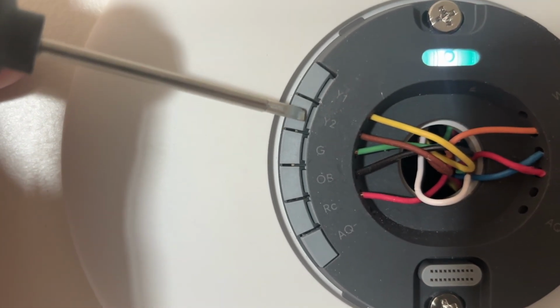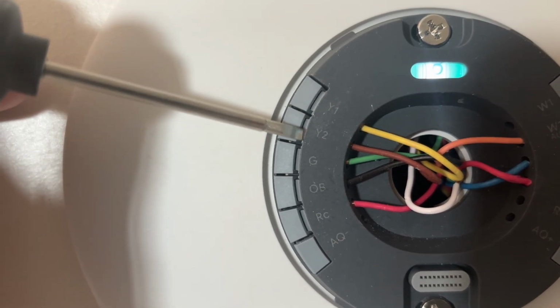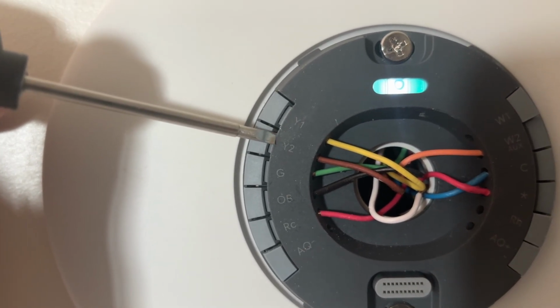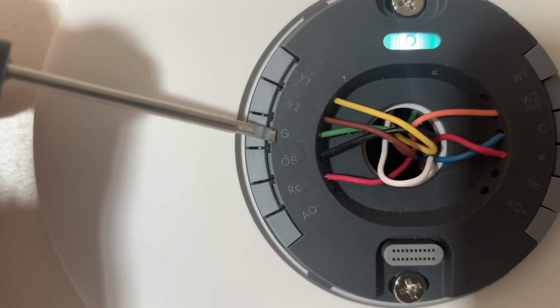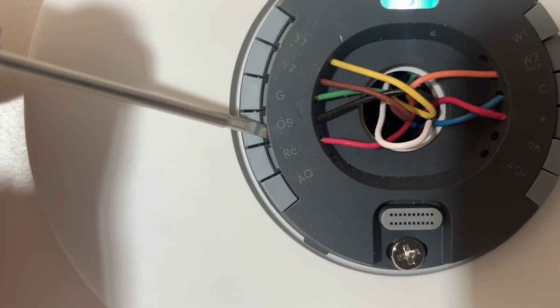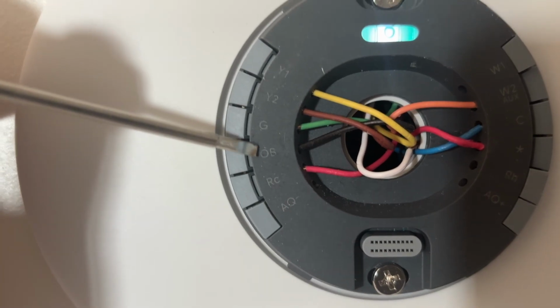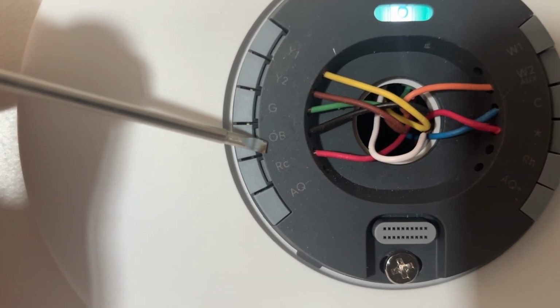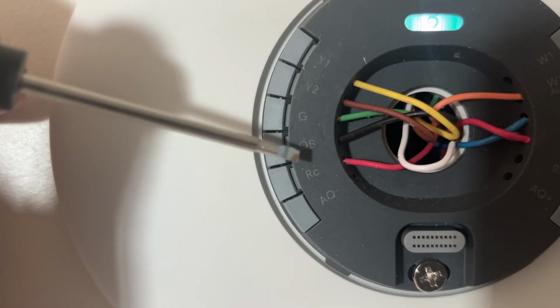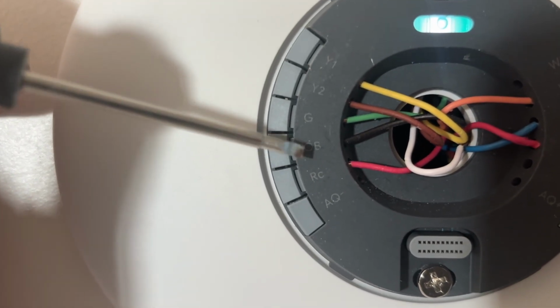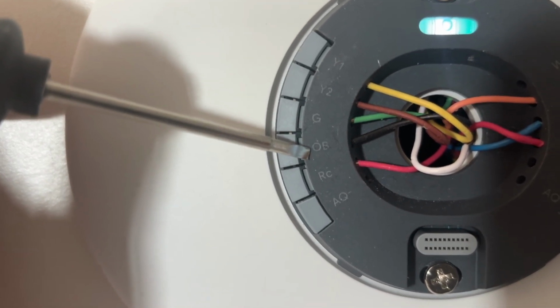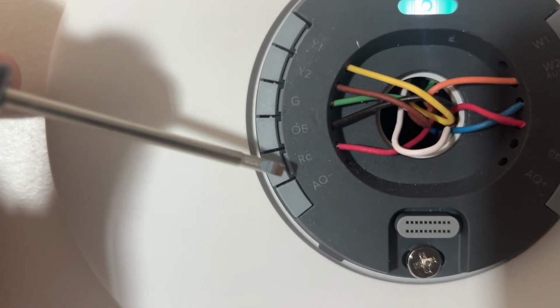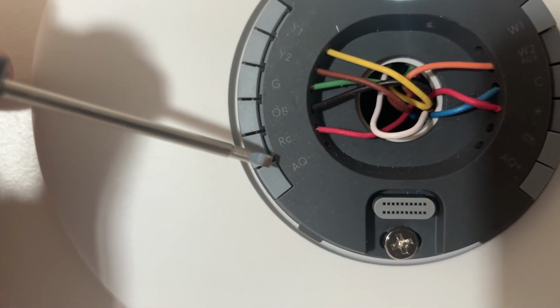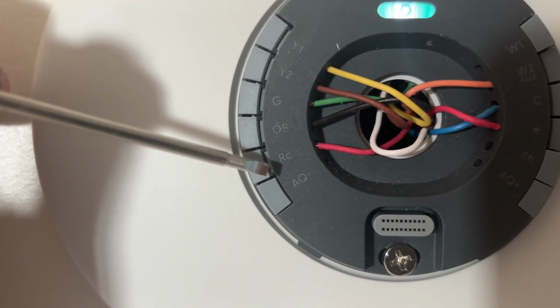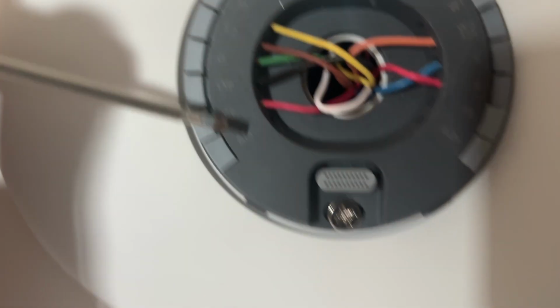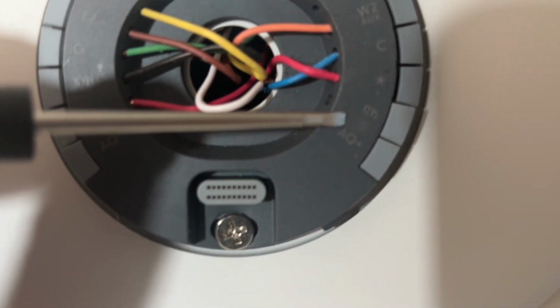Y1, Y2, we've talked about: stage 1 heating and cooling, stage 2 heating and cooling, depending on the reversing valve. G is for the fan control. OB is the reversing valve, and again, there are two different configurations here. You can have it set up for O or B configuration. The VersaPro, it says in the manual, is a B unit, so we have selected B configuration. As far as power to the thermostat, since we're a single transformer, you can either hook it into RC or RH.